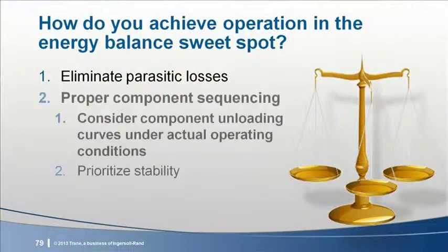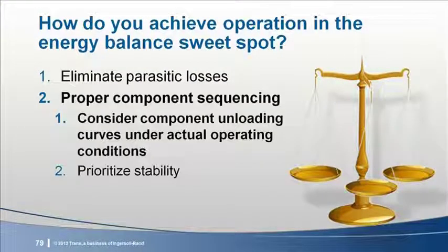The second step in controlling to the energy balance sweet spot is proper component sequencing. While adding variable speed drives to system components does not always dictate changing the sequencing logic, there are circumstances where a change in sequence can result in appreciable savings. Let's examine the effect of adding variable speed drives on the sequencing of two different components.